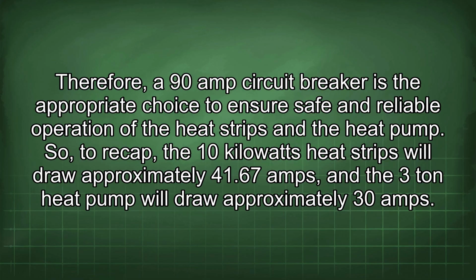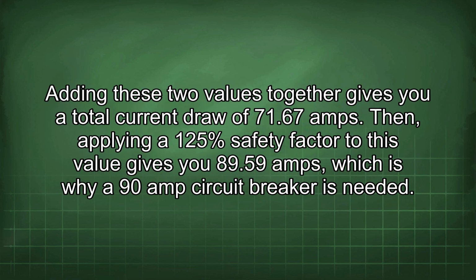So, to recap, the 10 kilowatt heat strips will draw approximately 41.67 amps, and the 3-ton heat pump will draw approximately 30 amps. Adding these two values together gives you a total current draw of 71.67 amps. Then, applying a 125% safety factor to this value gives you 89.59 amps, which is why a 90 amp circuit breaker is needed.